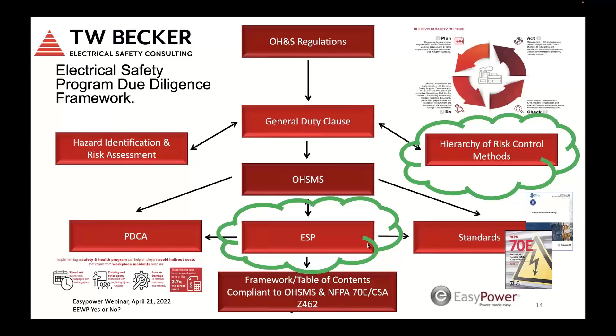Again, hazard identification, risk assessment, and an occupational health and safety management system is developed, and underneath it, a supporting electrical safety program for arc flash and shock hazards, using standard 70E or Z462 for the US or Canada. That plan, do, check, act philosophy is really an overarching, excellent philosophy that I like. We build this program based on what's expected for occupational health and safety management systems, and embed an energized electrical work permit policy in our company's electrical safety program.